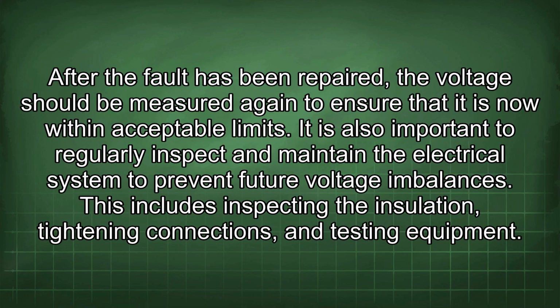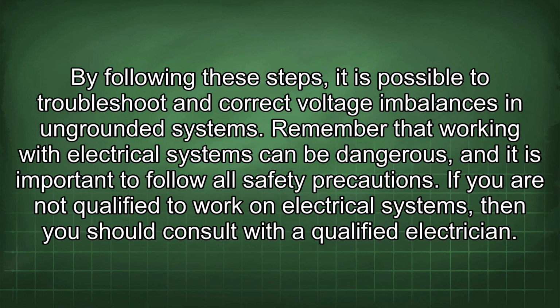After the fault has been repaired, the voltage should be measured again to ensure that it is now within acceptable limits. It is also important to regularly inspect and maintain the electrical system to prevent future voltage imbalances. This includes inspecting the insulation, tightening connections, and testing equipment. By following these steps, it is possible to troubleshoot and correct voltage imbalances in ungrounded systems. Remember that working with electrical systems can be dangerous, and it is important to follow all safety precautions. If you are not qualified to work on electrical systems, then you should consult with a qualified electrician.